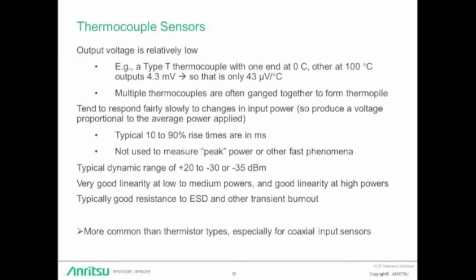So, the positives and negatives of thermocouple architecture. In thermocouple sensors, the output voltage from a thermocouple can be relatively low. A T-type thermocouple might only output 43 microvolts per degree C. So often multiple thermocouples are ganged together to form a thermopile, resulting in higher net output voltage, which is easier to measure. Like thermistors, thermocouple-based sensors are fairly slow, with rise times in the millisecond range. As a result, they are not used to measure peak power or other fast phenomena. We will discuss peak power in a few slides.